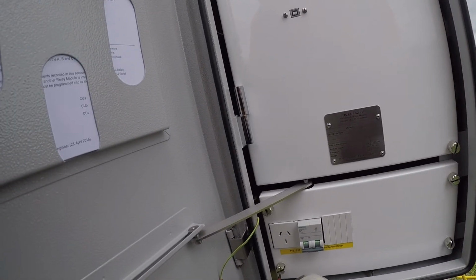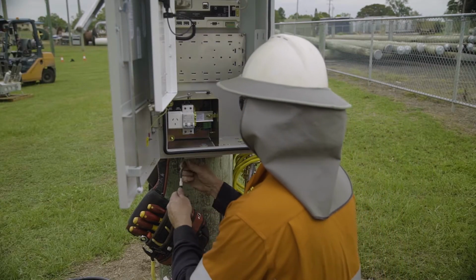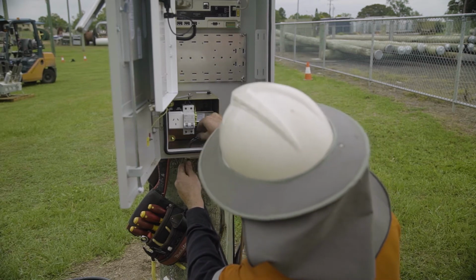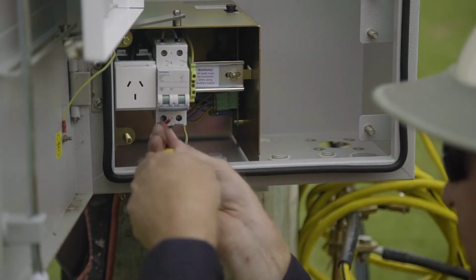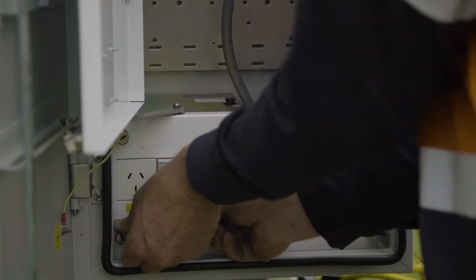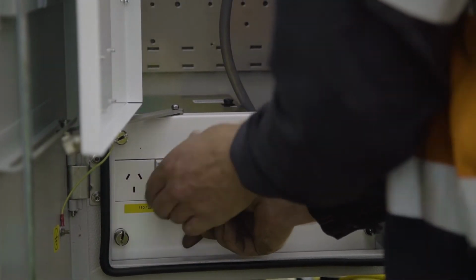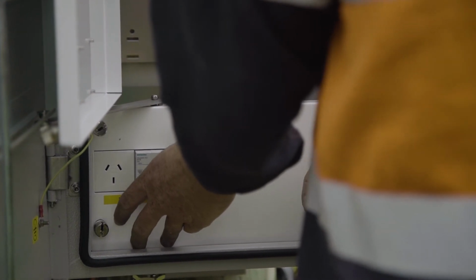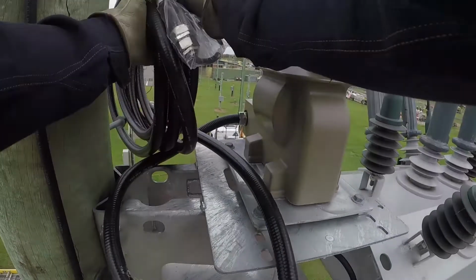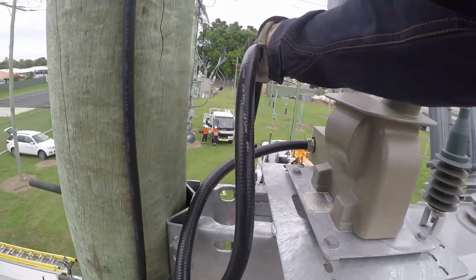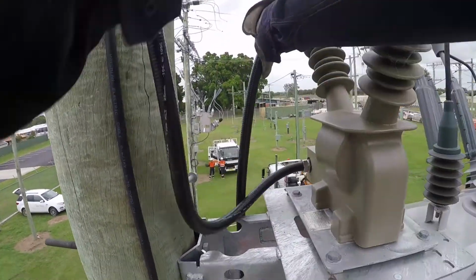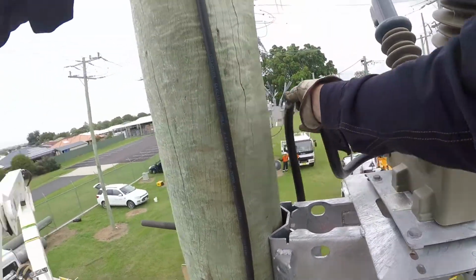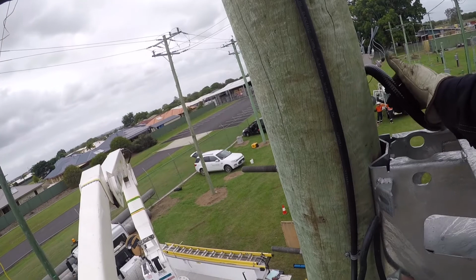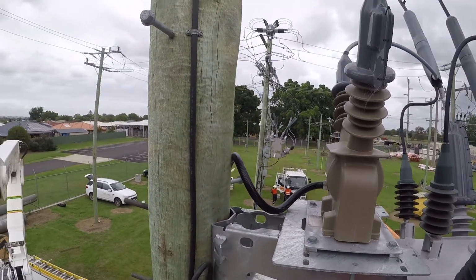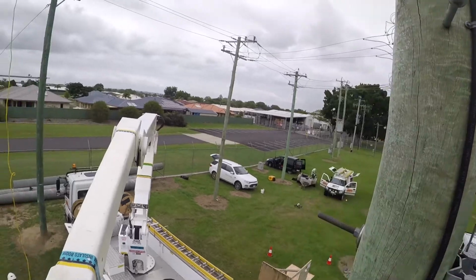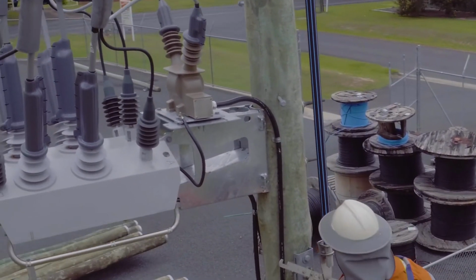The low voltage AC supply is used to keep the controller on. The low voltage AC supply is connected to the circuit breaker behind the lower escutcheon panel. The RC10 can accept either 110 or 220 volts AC. The voltage selection must be made with the circuit breaker in the off position if you are changing it. AC can be sourced from a dedicated voltage transformer like what you see here today, or alternatively from a low voltage line. NOJA Power's supplied voltage transformers are fitted with a 2 ampere fuse in the secondary wiring. It prevents the overheating of the secondary side if a short circuit occurs in the wiring down to the RC10.